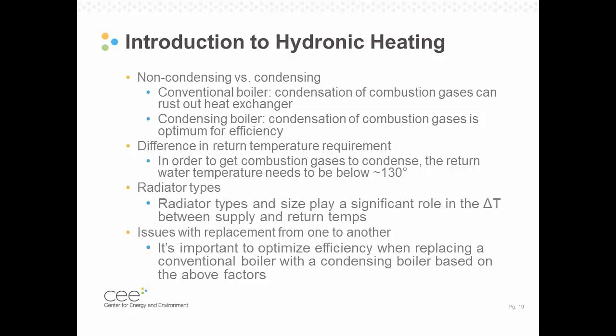The tipping point on where we get condensing or not is really based on the return water temperature. I'll go over a little bit of that in a second, but 130-degree water temperature is the tipping point between condensing or not. If the return water temperature is above 130 degrees, then you pretty much prevent condensation. If it's below 130 degrees, that's when you start getting condensation. The radiator types can really play a significant role in this, because the return water is a function of the supply water temperature, and so the more heat that can get delivered to the house through the radiators, the lower the return water temperature can be once it gets back to the boiler.